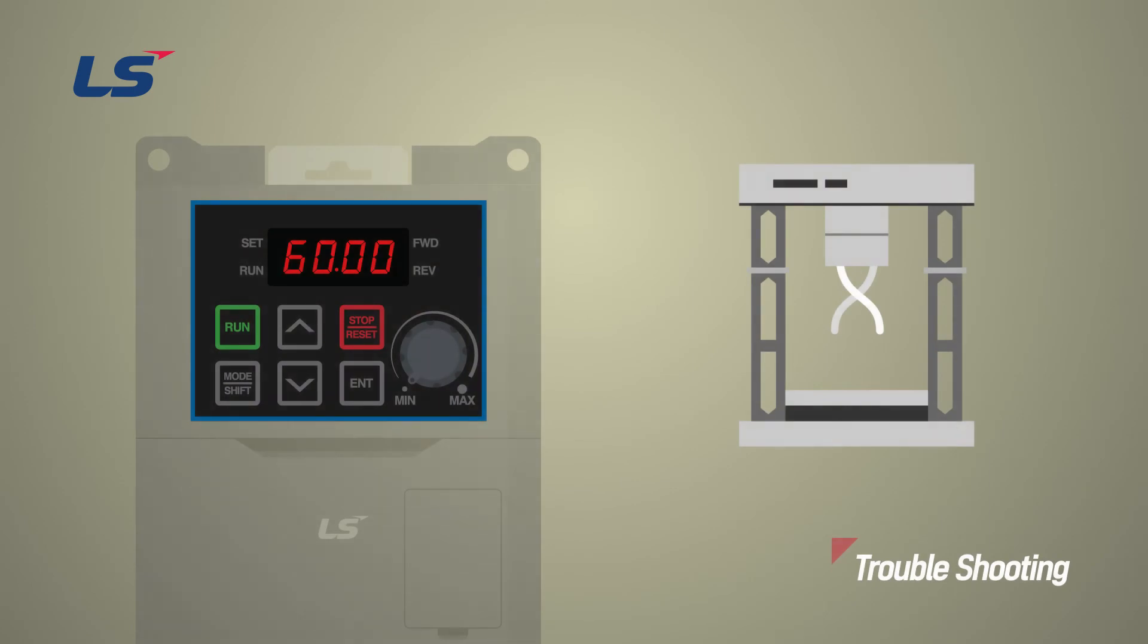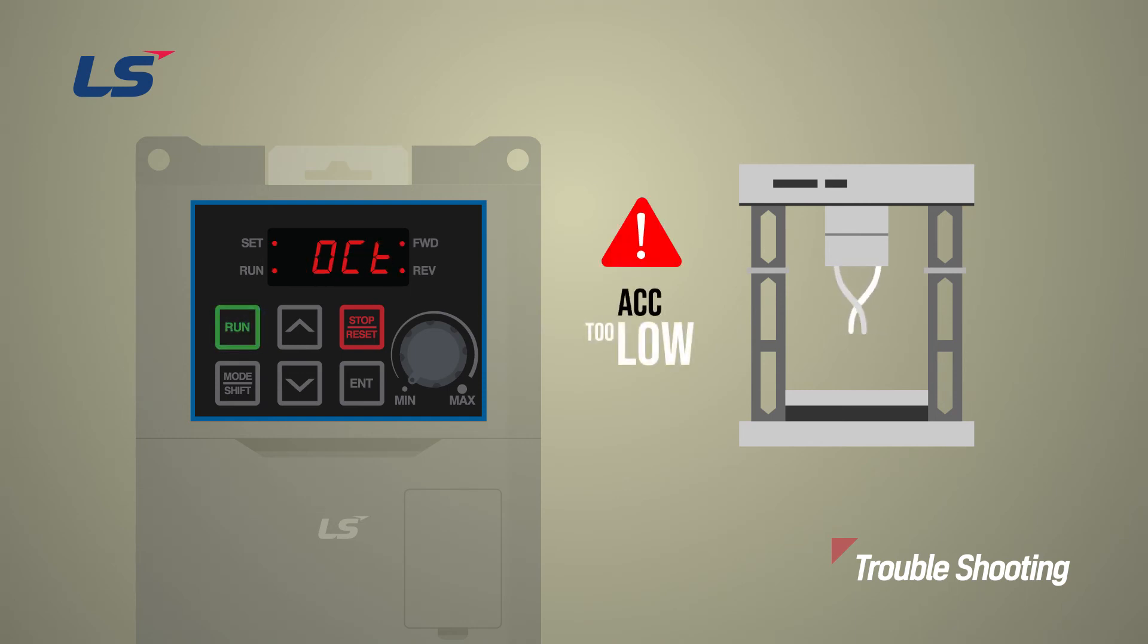If the acceleration and deceleration time is set too short, an inverter trip may occur. If the acceleration time is too short, it cannot overcome the load of the motor and an overcurrent trip may occur.